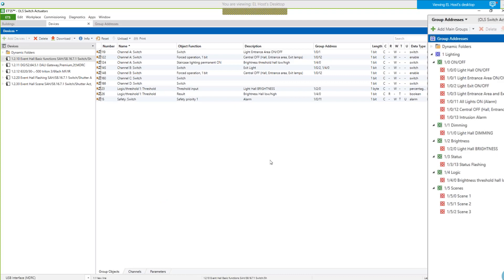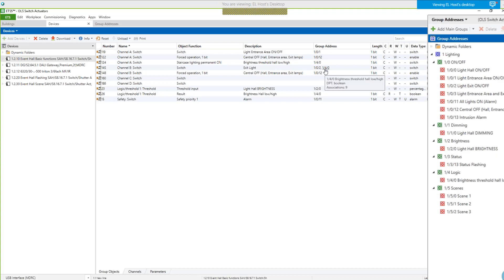Coming back to the group objects — the threshold input is the brightness status of my DALI lighting group, and I get directly the one-byte object information. So if I undershoot 30%, I send out the result of this threshold comparison — group address 1/4/0 — and I send it directly to turn on permanently the entrance area. I don't use the switch object with staircase lighting behind. I switch on permanently with a permanent on group object, so the light won't go off automatically anymore. The same applies for channel B, the exit light.